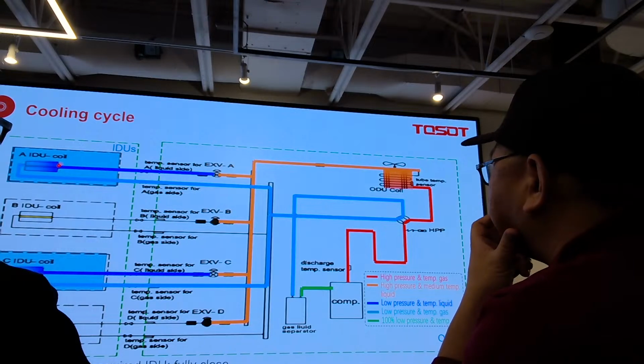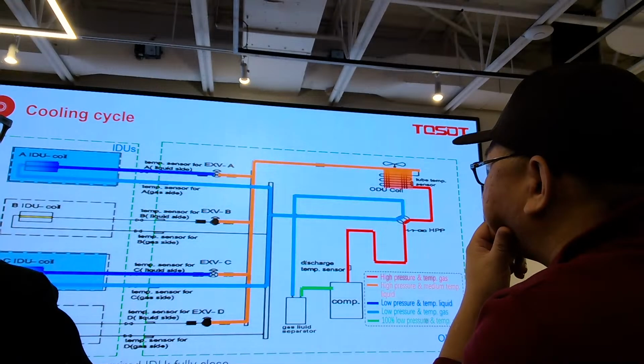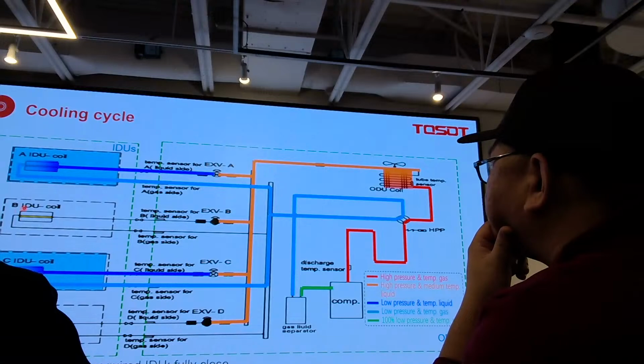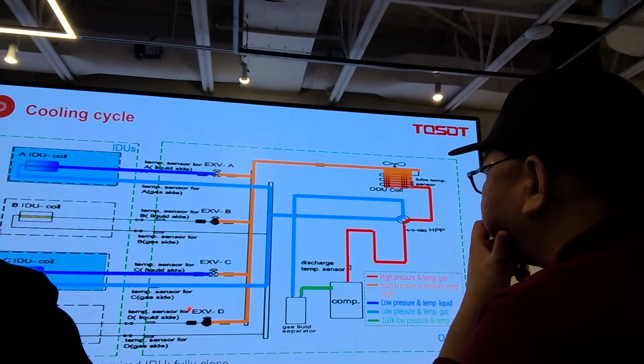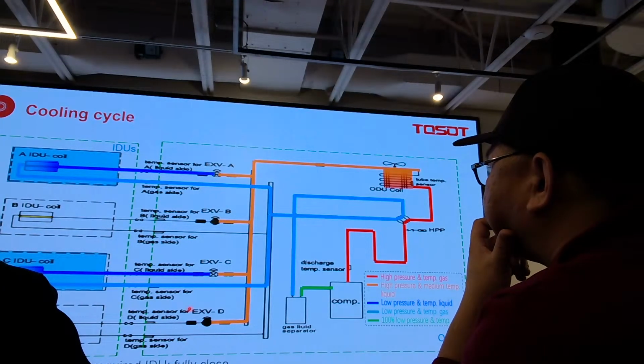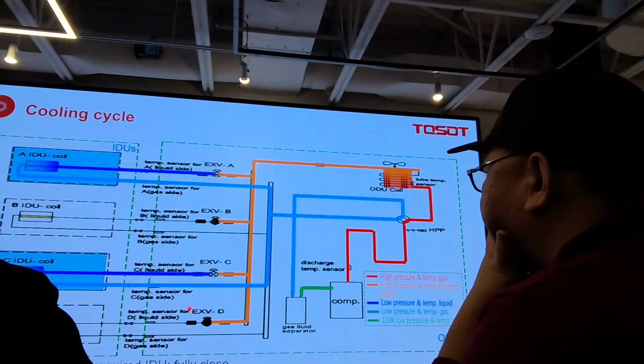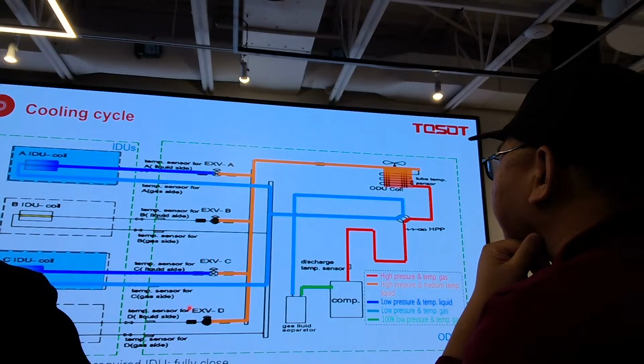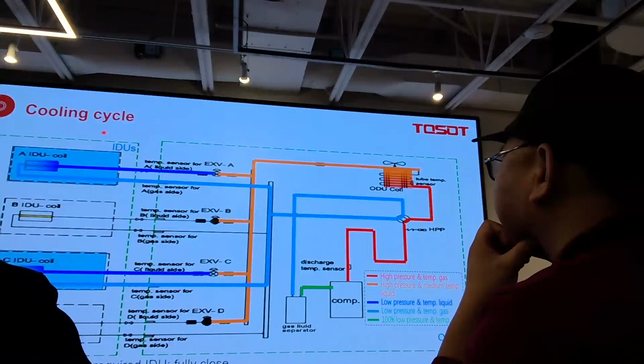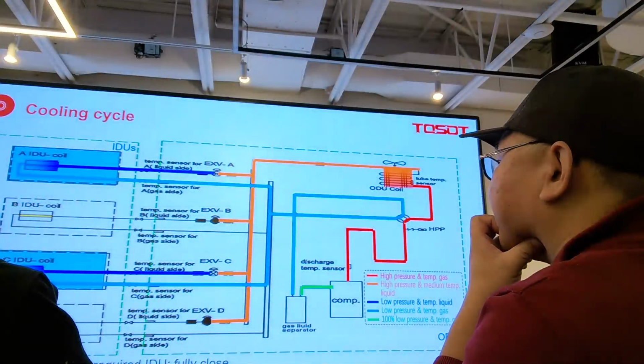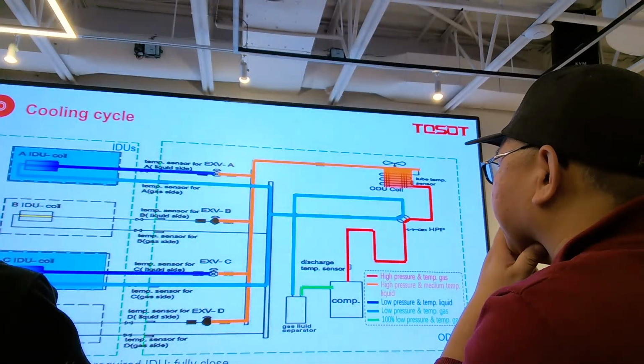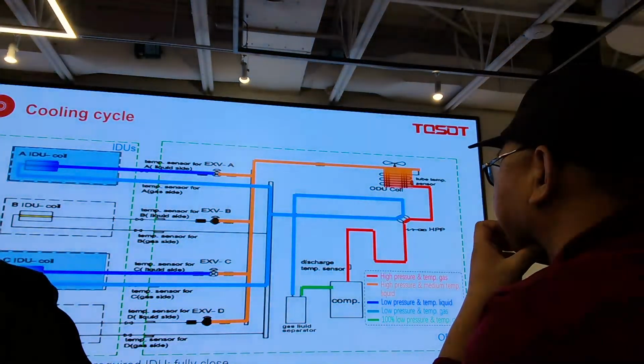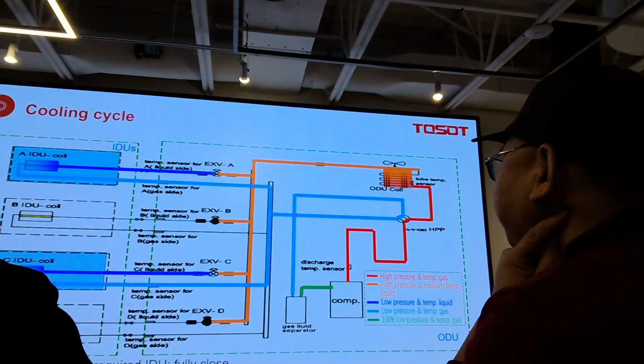And here is a question. How about for B and D, the EXV, how will it operate? I give you some options: fully open, fully closed. Which one? Fully closed. Fully open. Who says that? Attention, this is indoor unit B, indoor unit C, indoor unit D. There's no cooling required, so we will keep it fully closed. Then there's no refrigerant flow through B and D.